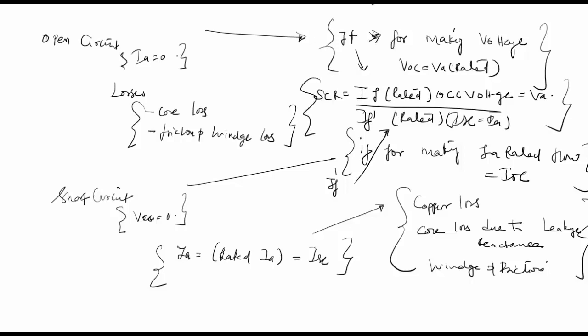Based on the parameters which you have found in the open circuit test and short circuit test, it is possible to have graphs between VOC to IF and these are known as open circuit curves. And again it is possible to have a graph of ISC to IF field current. These are known as the short circuit curves.